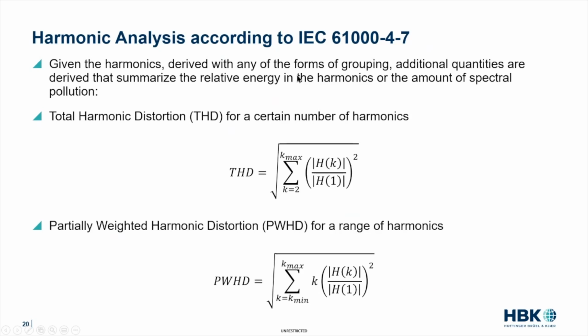As I said briefly, for the THD I'm talking about harmonics. As I mentioned, I can calculate the harmonics in three different ways: without grouping, sideband grouping, and full grouping. So if I know that, then I also have three flavors of my THD, namely based on harmonics calculated using no grouping, sideband grouping, and full grouping. In the same way I have three flavors of my PWHD. So that depends on how you calculate the harmonics.